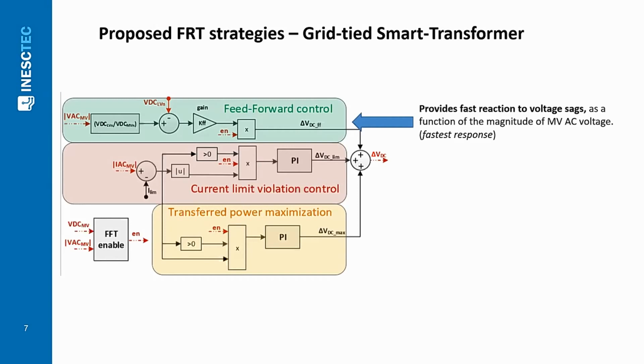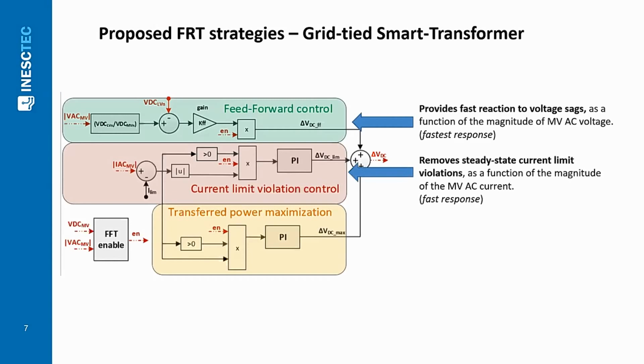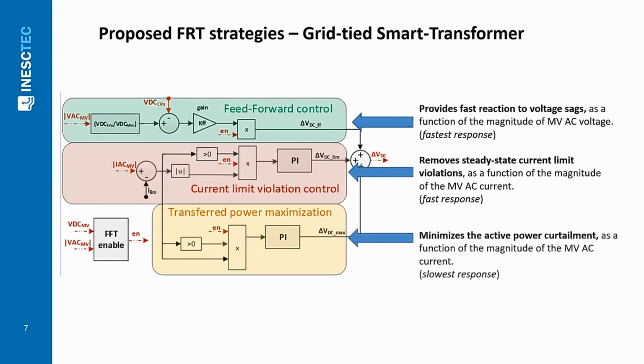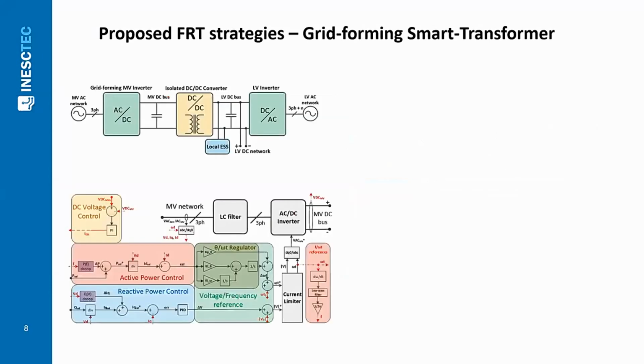The feed-forward control provides a fast reaction to voltage sags. Its output is calculated as a function of the AC voltage measured in the medium voltage inverter. The current limit violation control is focused on removing any steady-state current limit violation in the medium voltage inverter. Its output is calculated as a function of the output current in the medium voltage inverter. Finally, the transferred power maximization aims to minimize the active power curtailment in the hybrid distribution network. Its goal is to compensate for excessive activation by the two previous control structures.